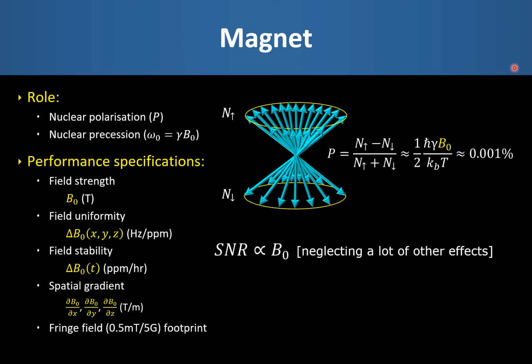We also need to consider the fringe field from the magnet. Current MR safety guidelines state that the fringe field must not exceed 0.5 millitesla or 5 Gauss in any adjacent publicly accessible areas, such as corridors or rooms adjacent to the MRI system. The space that contains the 0.5 millitesla field is known as the MR environment. This may mean that additional static magnetic field shielding may be required in the walls, or possibly even the ceilings or floors of the MR environment, depending on adjacent areas, which may contain equipment that is particularly sensitive to magnetic fields, such as photomultiplier tubes in nuclear medicine gamma cameras.